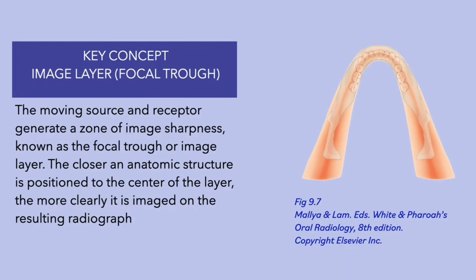A key concept in panoramic imaging is the formation of the image layer or focal trough. By moving the source and the receptor, we generate a zone of image sharpness. This zone is referred to as the image layer or focal trough. Objects that are located within this image layer cast sharp images. The closer an anatomic structure is located to the center of the layer, the more clearly it is imaged on the panoramic radiograph.